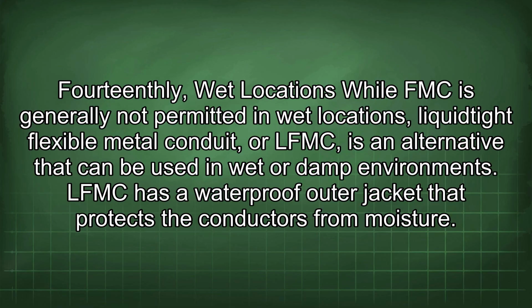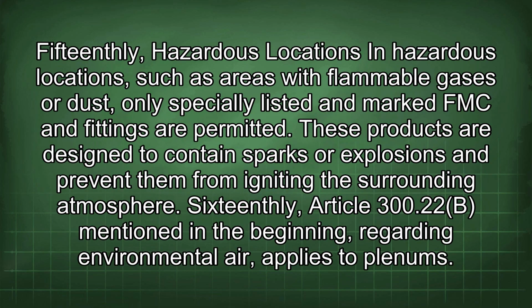LFMC has a waterproof outer jacket that protects the conductors from moisture. 15thly, hazardous locations. In hazardous locations, such as areas with flammable gases or dust, only specially listed and marked FMC and fittings are permitted. These products are designed to contain sparks or explosions and prevent them from igniting the surrounding atmosphere. 16thly, Article 300.22(B), mentioned in the beginning, regarding environmental air, applies to plenums.